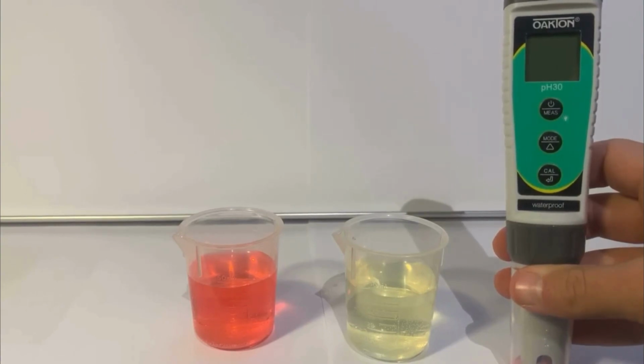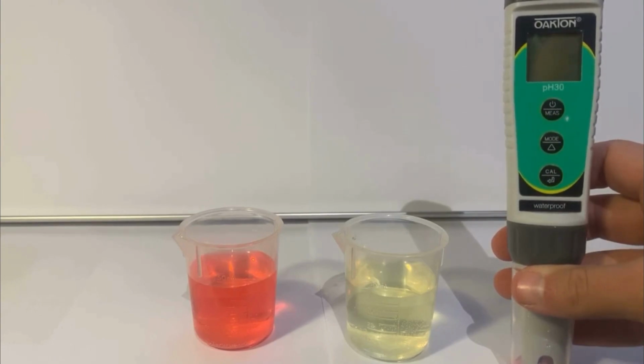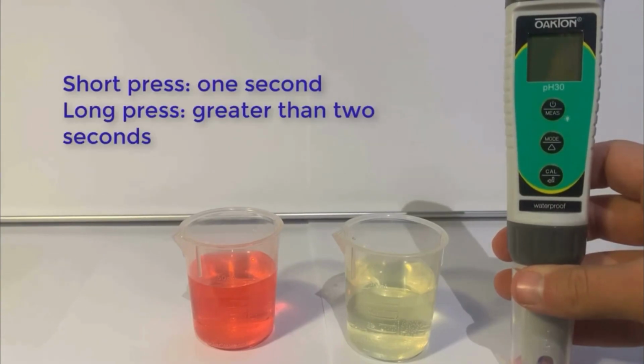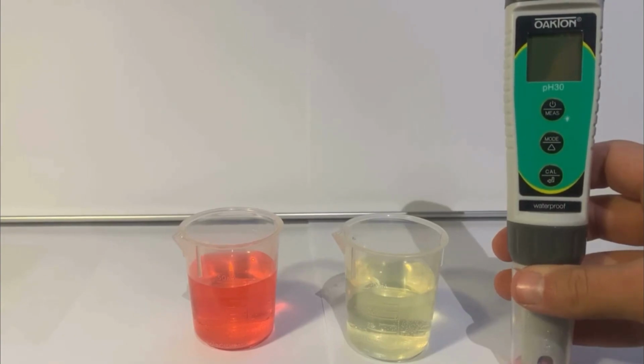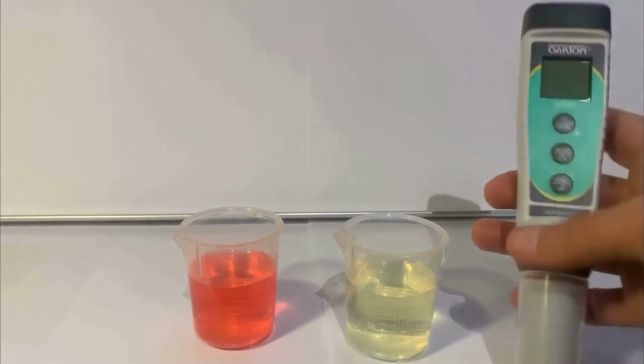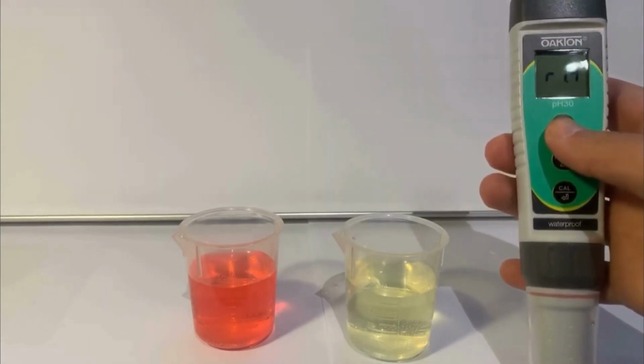So today we are using Buffer 4 and Buffer 7 to calibrate. 4 is in red and 7 is in yellow. Make sure that you use the solutions that bracket your normal reading when you calibrate. We will be using the long press and the short press on the buttons today. A short press is a quick 1-second press, and a long press is holding the button down for about 2 seconds. So short press the power button to turn on your meter. You can short press this button again at any time to turn on the blue backlight on your screen if it helps you see.